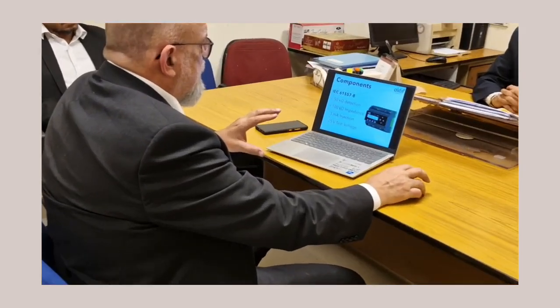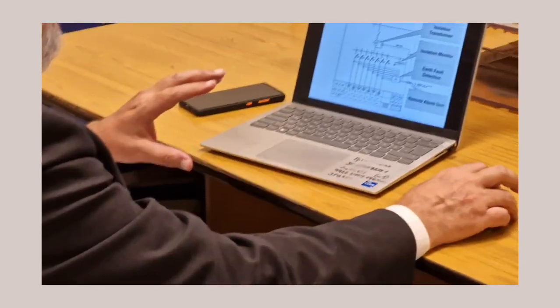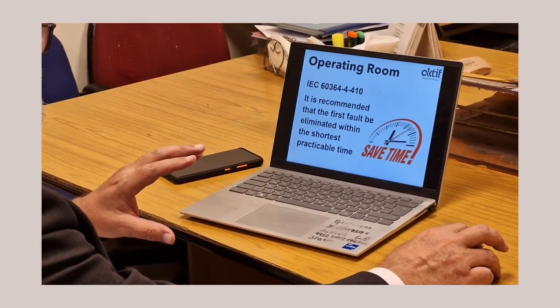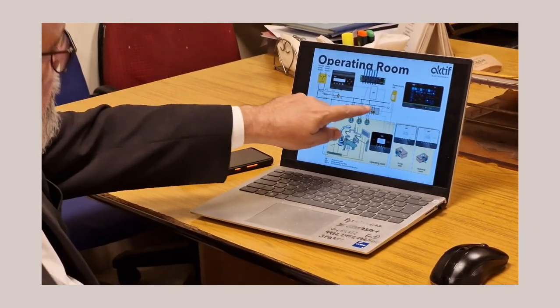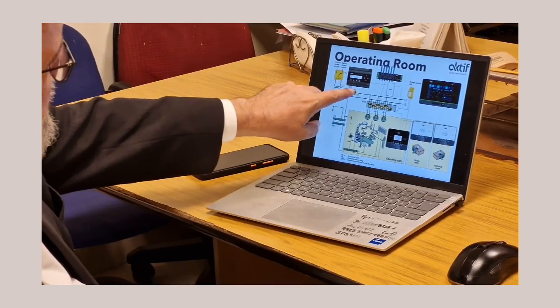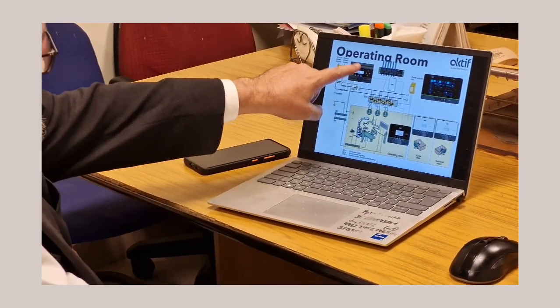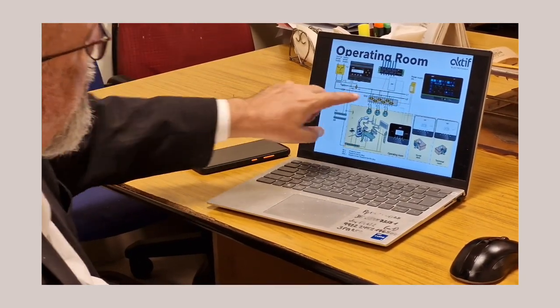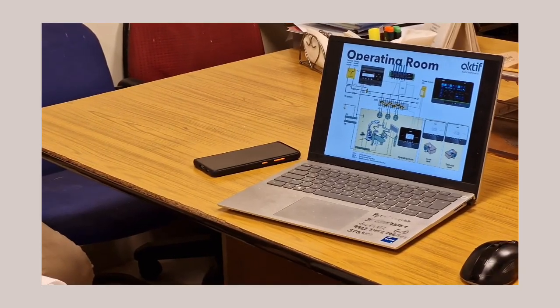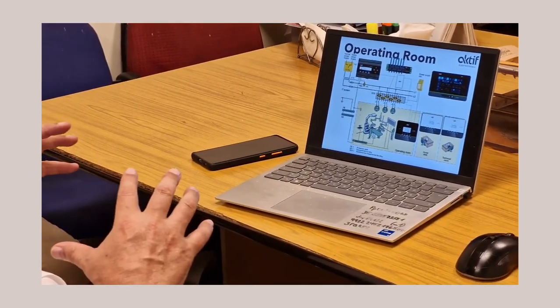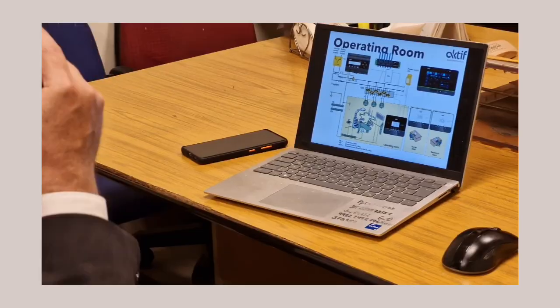But, sorry that I go a little faster, we have a setup where we have the insulation monitor installed, but in addition we install an earth fault detection system. So the insulation monitor tells you there is a problem in this ICU room, and the EDS tells you it's that socket. Exactly. Yes. And we have to rush to that point where the problem is and get it rectified.